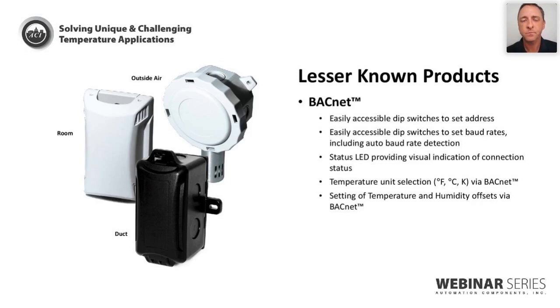Lastly, we have BACnet MSTP communicating sensors. Very easy to set up, address, and get connected to your network. So we're seeing more and more applications and requirements for just monitoring, or if you don't want to use up additional inputs on your controller, you can get a temperature or humidity sensor and get it on your network. And it's a very cost-effective way to do that.